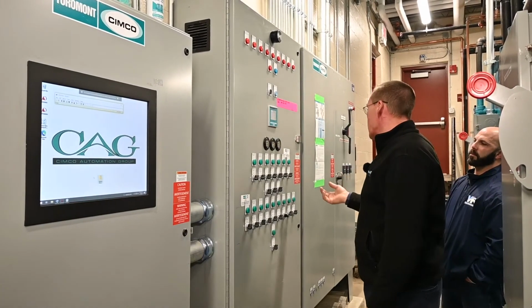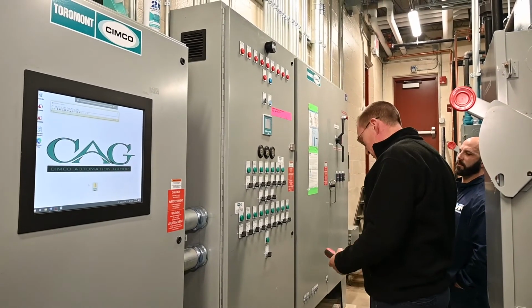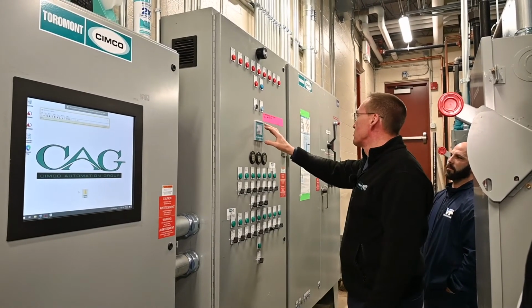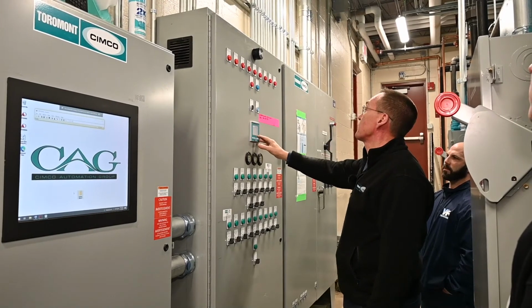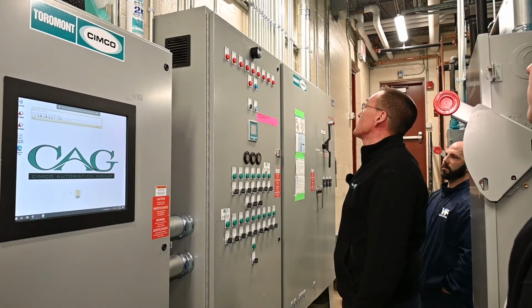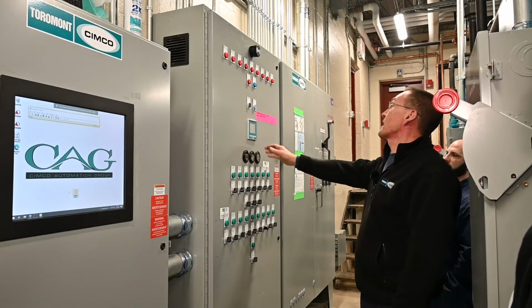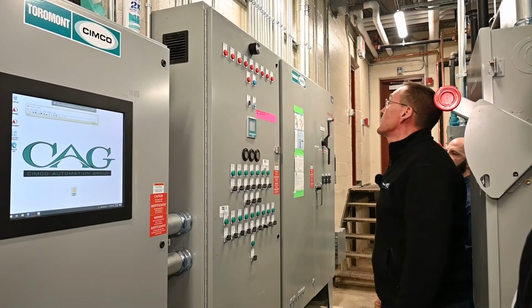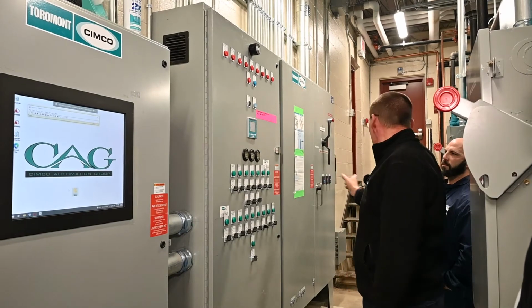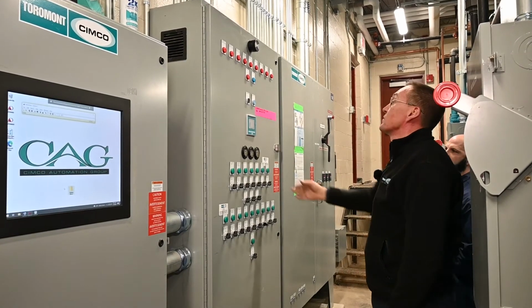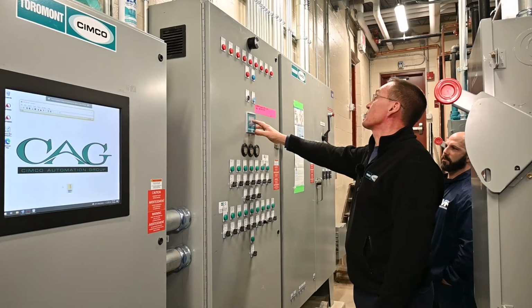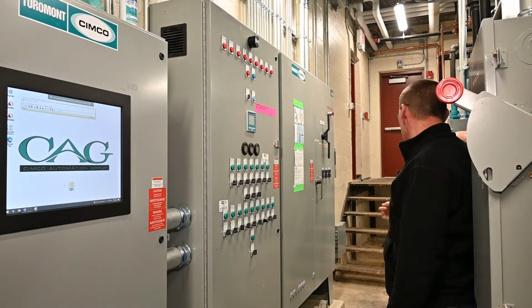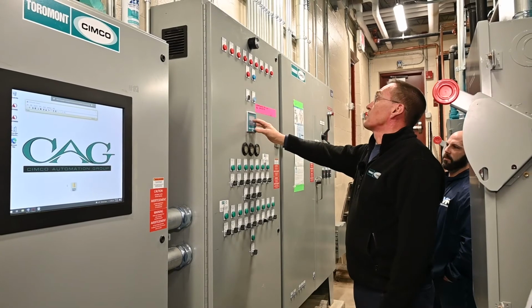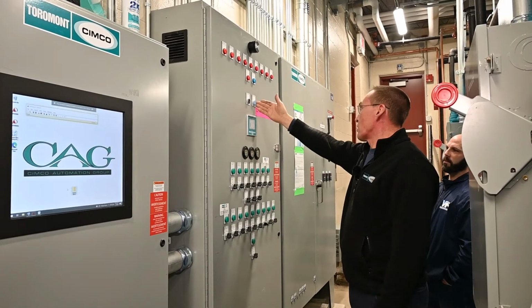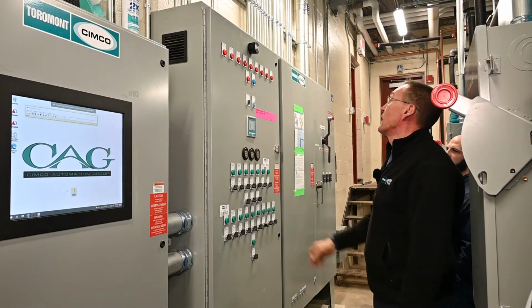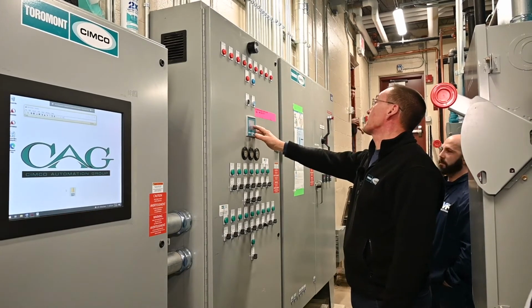In the case that that doesn't happen, or we request that you do something, within this Unitronics touchscreen here, you have several different push buttons. Status is the first one, and within status, it gives you the general status of the system, whether or not we have a pump interlock from P1, P2, showing that we have flow for the system to run. DDC mode, that's the computer actually calling to run. Alarm silence, which in this case, if the alarm was going off, that light would be red. And then compressor 1, 2, or 3 is online.